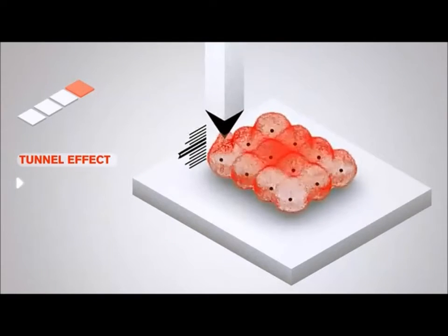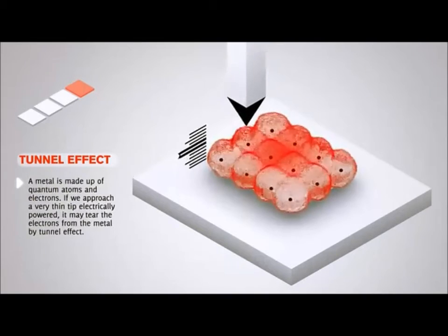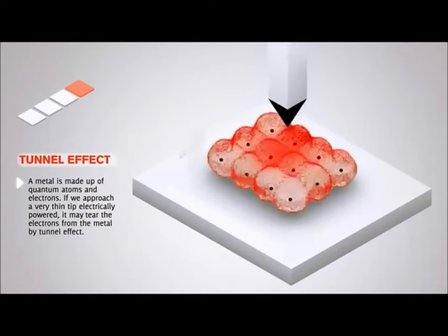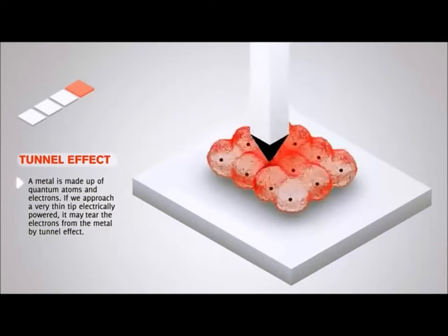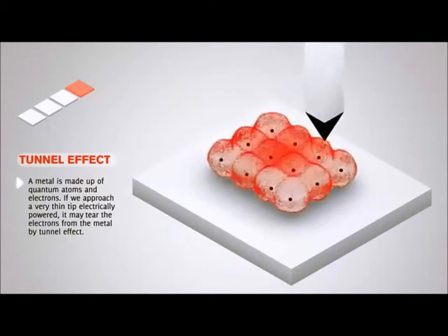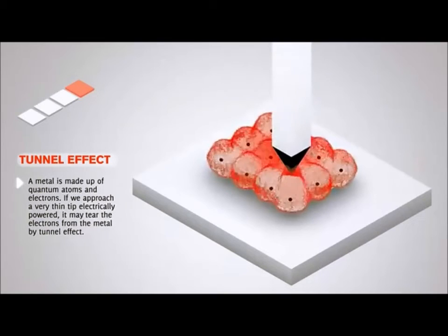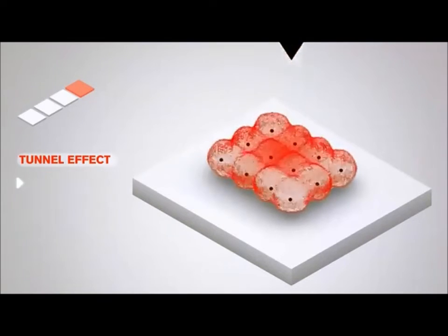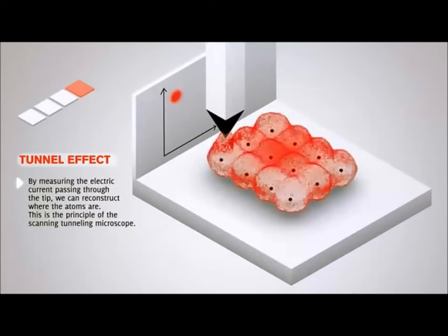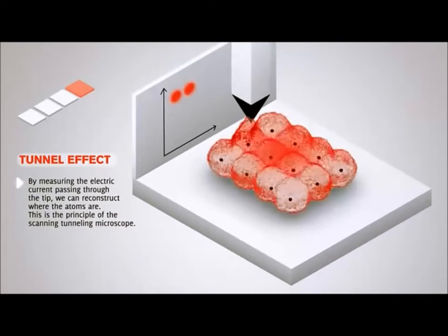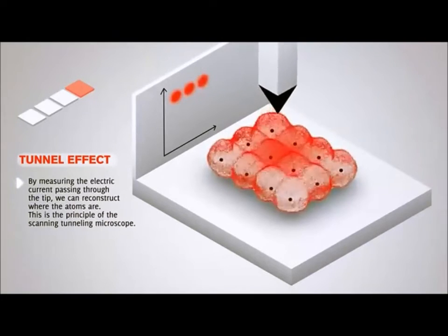In the scanning tunneling microscope, the sample is scanned by a very fine metallic tip. The scanning can be controlled in 3D by a piezo scanner, either bound to the tip or attached under the sample stage. The sample is positively or negatively biased so that a small current, the tunneling current, flows if the tip is in close proximity to the sample. This feeble tunneling current is amplified and measured.